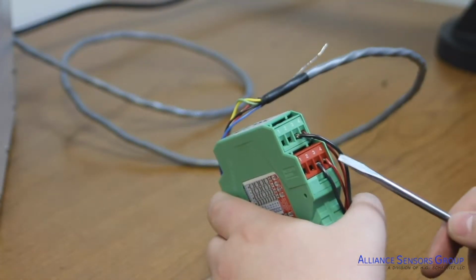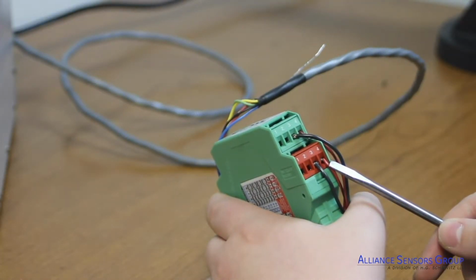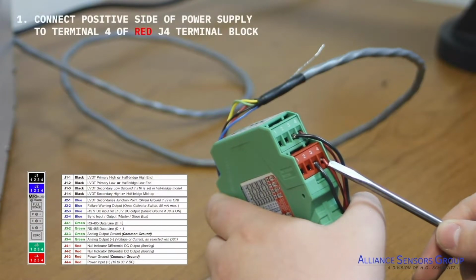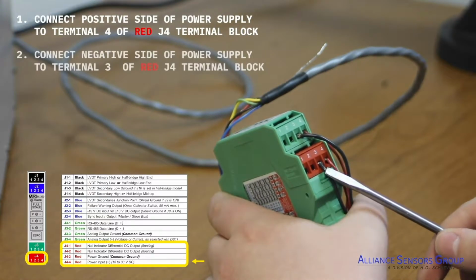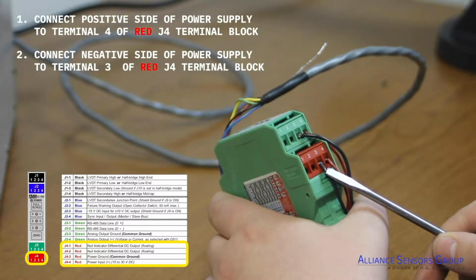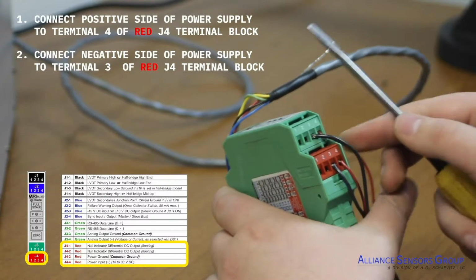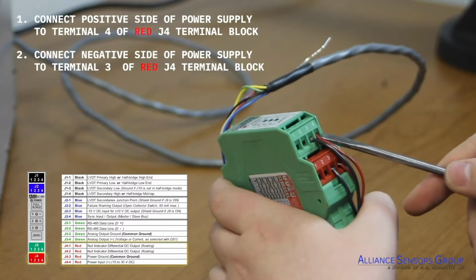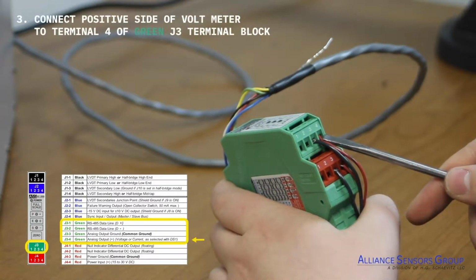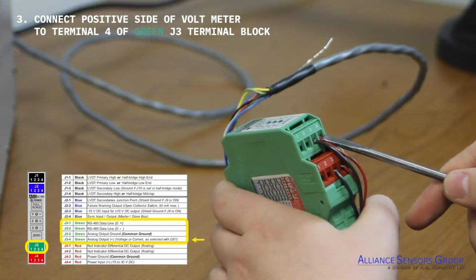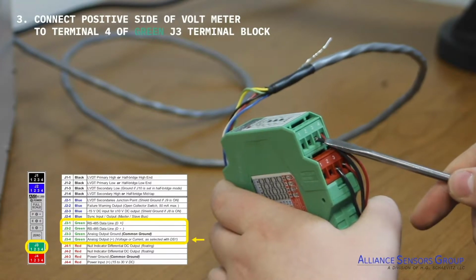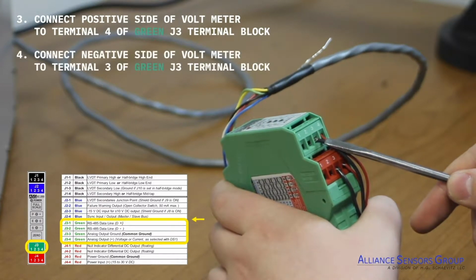After the internal dip switches have been set, begin by connecting the power supply. Connect the positive side of the power supply to terminal 4 of the red J4 terminal block, and the negative side of the power supply to terminal 3. Next, connect the digital voltmeter, which will measure the output from the SC-200. Connect the positive side of the voltmeter to terminal 4 of the J3 green terminal block, and the negative side of the voltmeter to terminal 3.